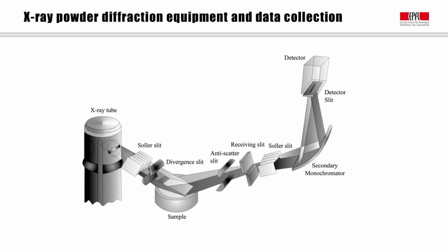Increasing the peak resolution often involves cutting a part of the incoming and reflected intensity that leads to peak broadening and thus reduces overall peak intensities. Thus, in practice, a compromise needs to be found among different data quality measures, also taking into account practical considerations such as the available time for measuring and the acceptable sample exposure time.